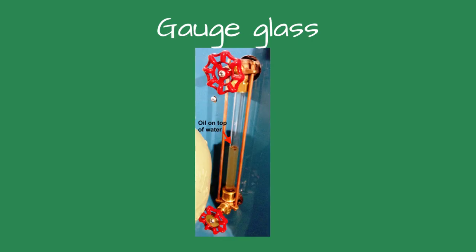I started the boiler and looked at the water in the gauge glass to see if there was oil on top of the water or solids floating in the water. Oil or elevated solids could cause bouncing water levels in the steam boiler.